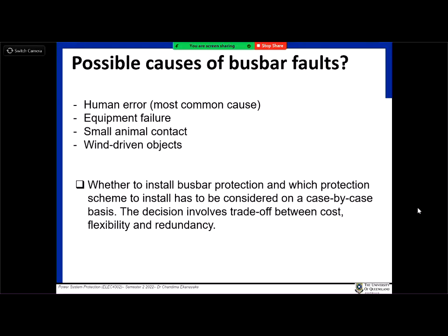Then huge short circuit, right? And they take all the spanners and all, and they forget to take them. Yes. So human error, and then the spanners and all those metallic tools, sometimes they leave them on the bus bar, right?